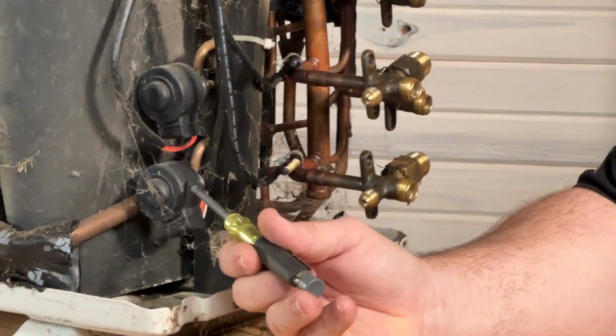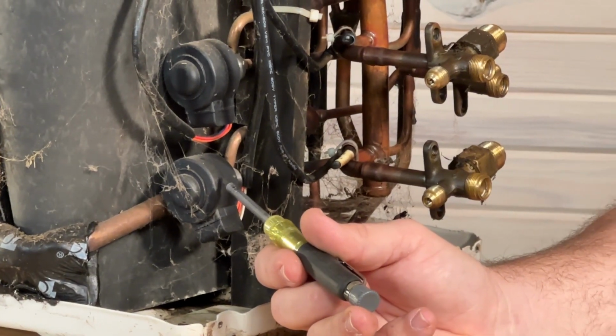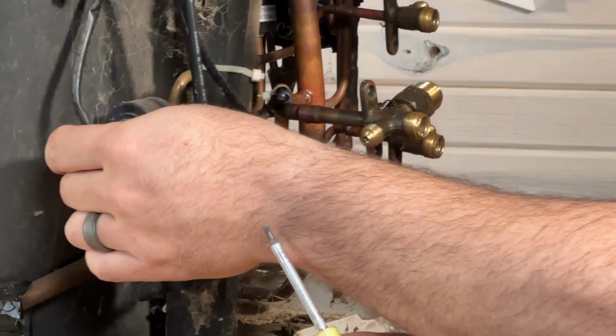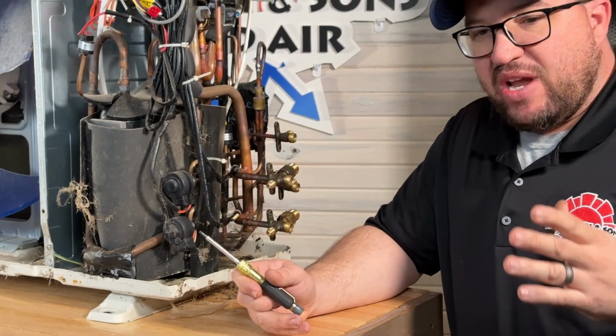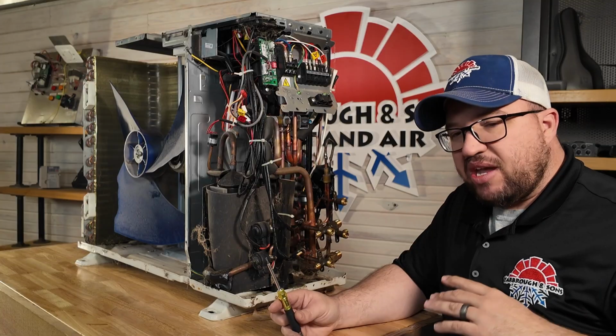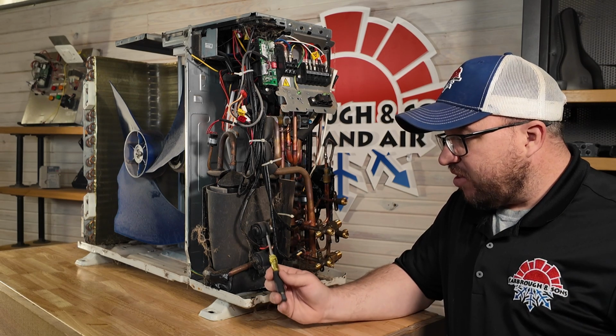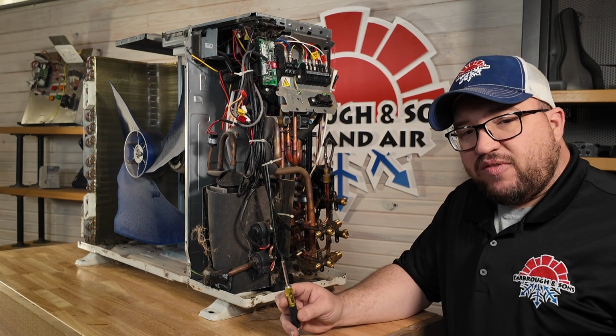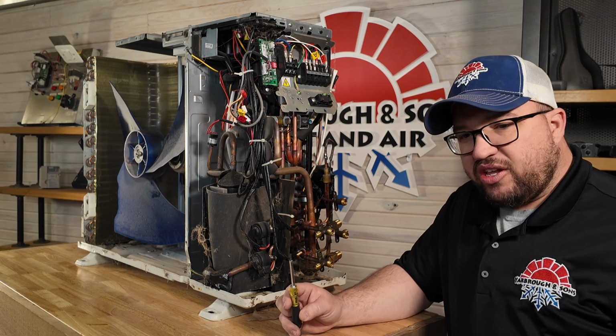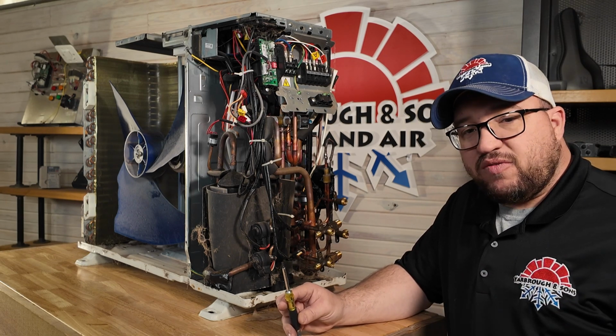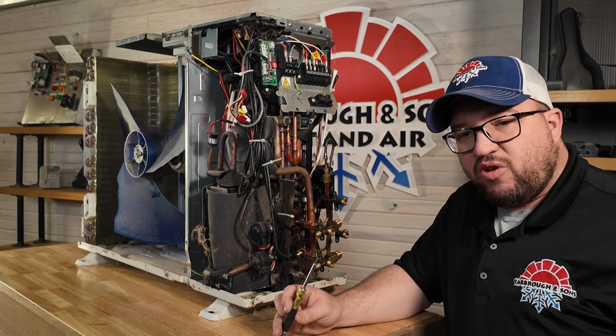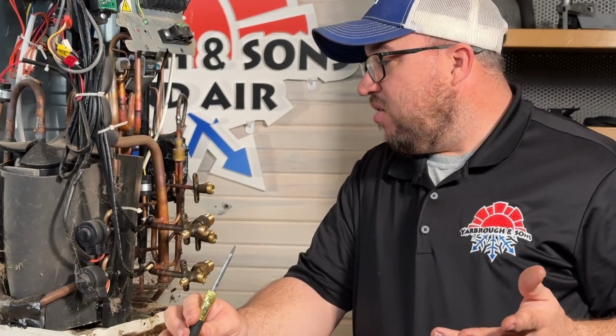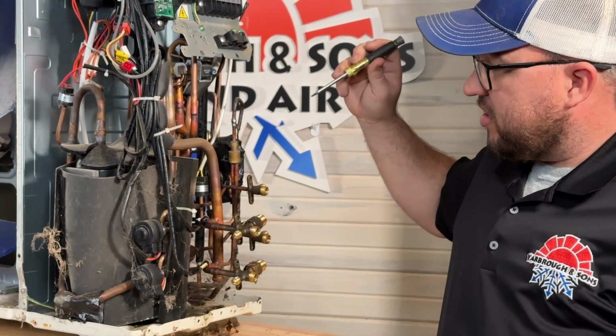EEVs are great. They're electronic expansion valves. That's what EEV stands for. That can actually improve your efficiency quite a bit because we have full control of this system to where we can actually calculate what your superheat needs to be with these EEVs and adjust it accordingly. That's going to make it super efficient. So great to have them on there. They are a little bit of work if you want to work on them. It takes a little bit of knowledge. It's not too much. You can find how to work on the actual EEV in any service manual for these.